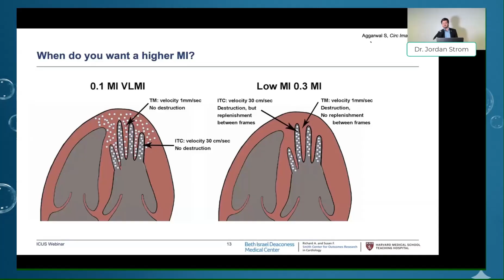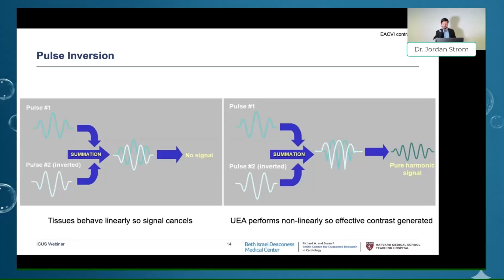Now, there are a couple of techniques that are really important to understand, and this is one of the reasons why if we take a regular ultrasound image and turn down the MI, that is not the same as doing a dedicated contrast imaging technique. And that is because there are several techniques that have been developed to be able to suppress the signal from the myocardium even further. So one is this technique called pulse inversion, and this is where two pulses are sent out simultaneously, but one of them is the inverse of the other. And so if you add them together, they produce no signal. And in myocardium, which largely behaves linearly, those signals cancel out. And so you basically get no signal from the myocardium, but you do from the blood pool where the ultrasound contrast performs nonlinearly. And that allows you to have a pure signal and effective contrast generation.